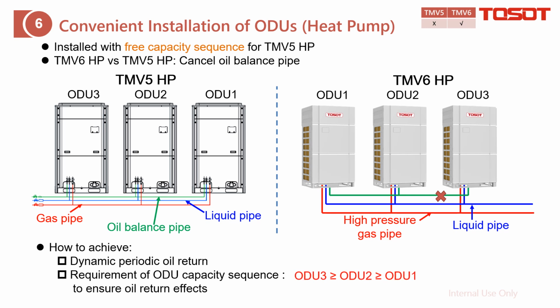In this case, if an outdoor unit is close to the indoor unit in this pipeline system, then its capacity should be bigger. The reason is that for oil return, the system raises the compressor frequency to use the refrigerant gas to flush the oil trapped in the indoor unit back to the outdoor unit through the gas pipe. So we find that more oil will flow to the first corner. In this case, outdoor unit 3 can get more oil.